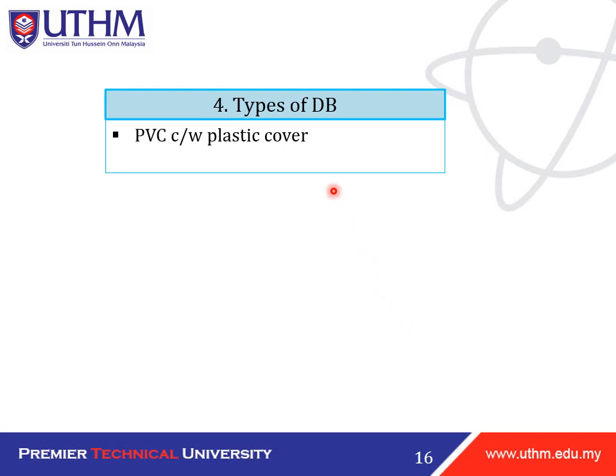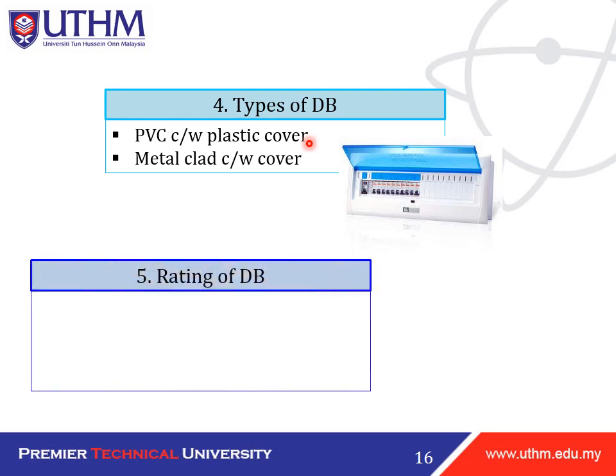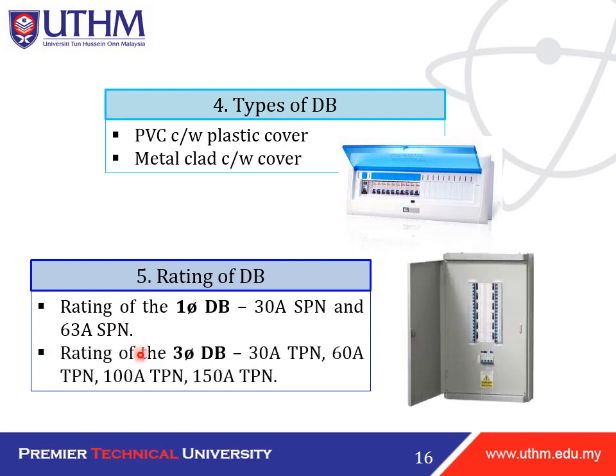Okay, for the types of DB, we have PVC type, covered with a plastic cover, and then we have metal clad, covered with a metal cover. And then for the rating of DB, we have the rating of the single phase DB, for example, 30 amp single pole and neutral, and 63 amp single pole and neutral. And then the rating of the three phase DB can be 30 amp three pole and neutral, or 60, 100 or 150 three pole and neutral type.